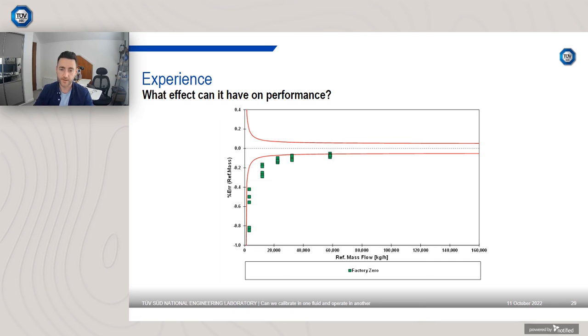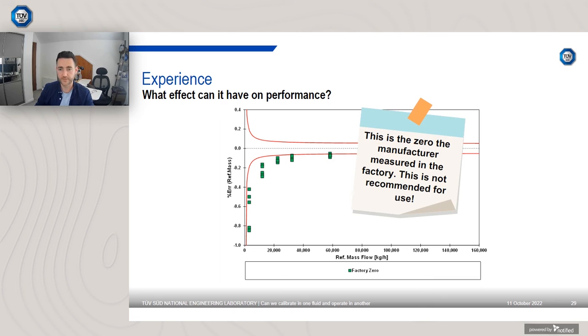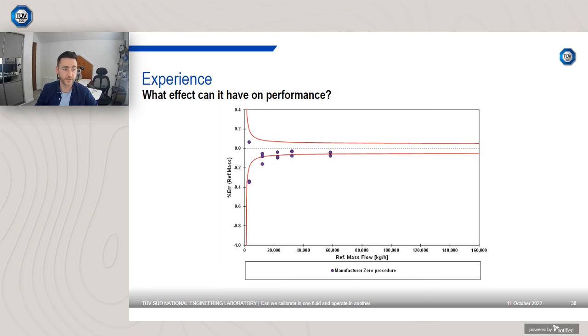It's always good to compare that factory zero with the zero that you are determining in your installation, because it should be fairly close to it. You don't want a significant shift. It should hopefully be fairly stable, giving you more confidence that it's a very good meter. When I reset it to the factory zero, you've seen it was outside of specification, which again was quite surprising, but we were at elevated conditions here, so maybe that had slightly affected the zero that we were perceiving. Again, this is the zero the manufacturer measured in the factory. It's not recommended for use. I'm just doing this to show you the effect of not correctly zeroing your device.